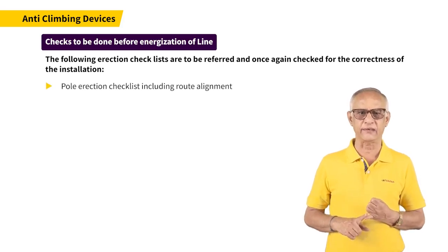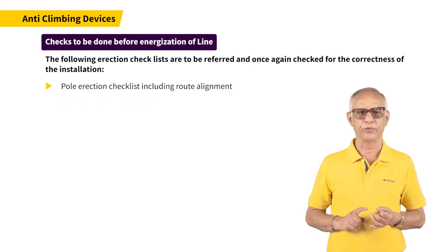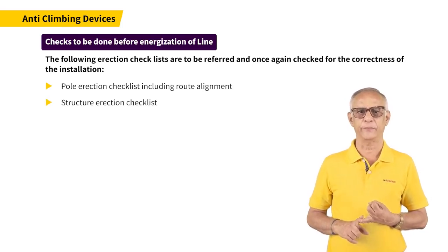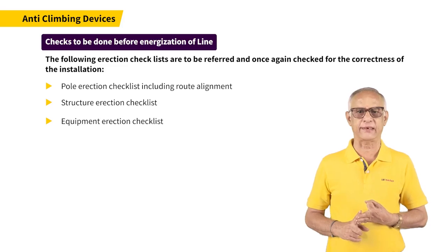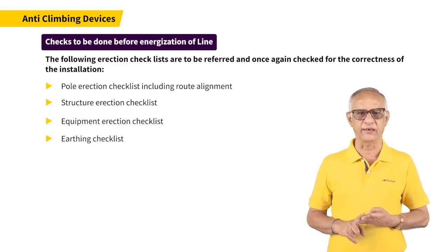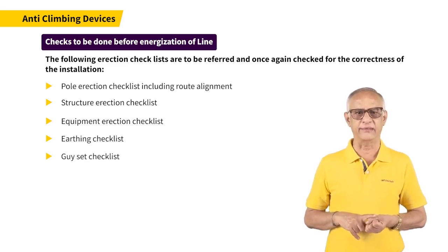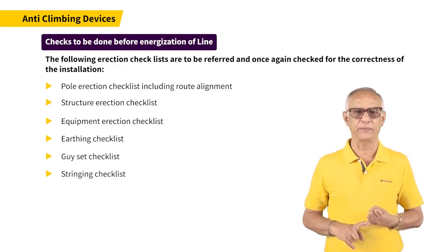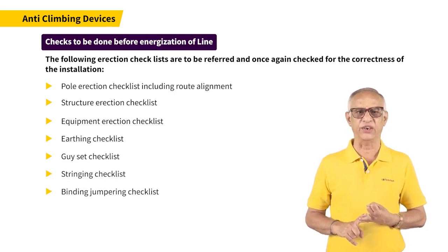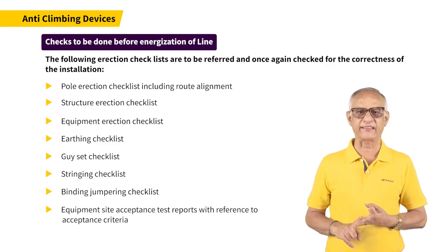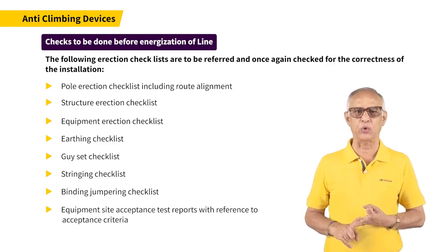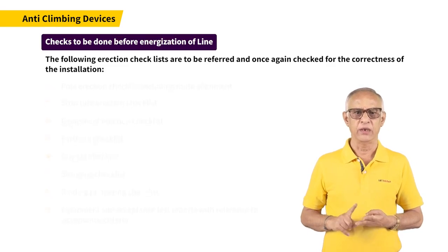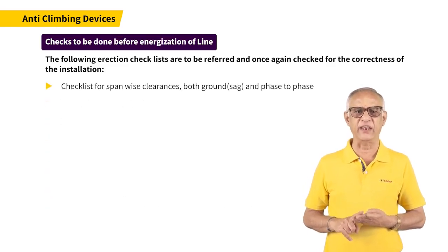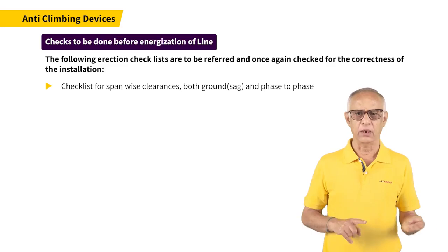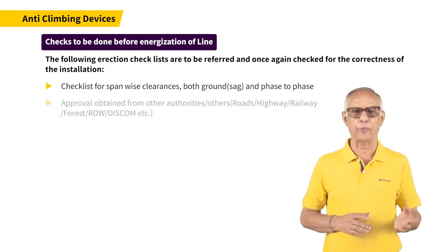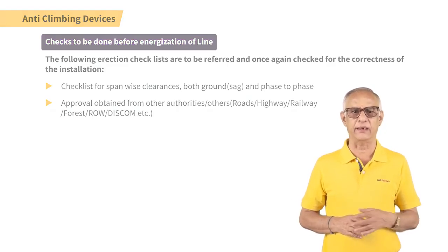Pole erection checklist including route alignment, structure erection checklist, equipment erection checklist, earthing checklist, guy set checklist, stringing checklist, binding, jumpering checklist, equipment site acceptance test reports with reference to acceptance criteria, checklist for span-wise clearances both ground and phase to phase, approval obtained from other authorities.